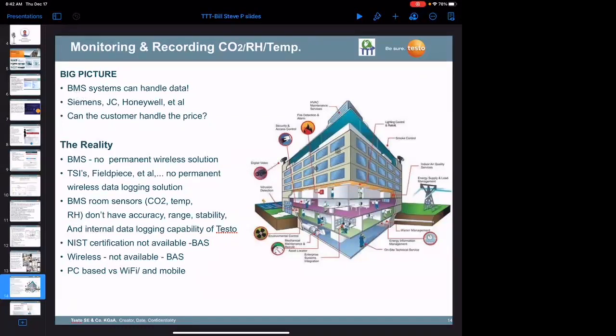It's pretty much the nervous system supplied by big temperature control contractors like Siemens, Johnson Controls, Honeywell, and others. They do amazing stuff: measure and control the fire detection and alarm system, monitor security and access controls, monitor CCTV output for burglary or break-ins, and control lighting throughout the building. You might have light sensors on the east and west sides, and the system will sequence the building lights with the morning sun or the afternoon sun, and vice versa.